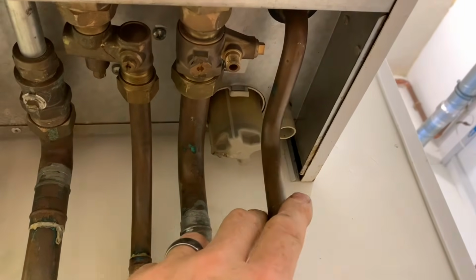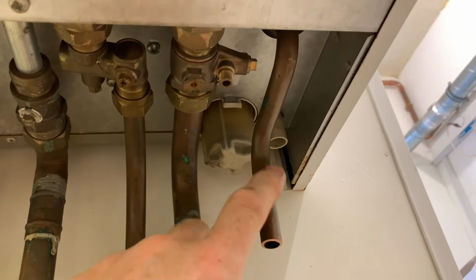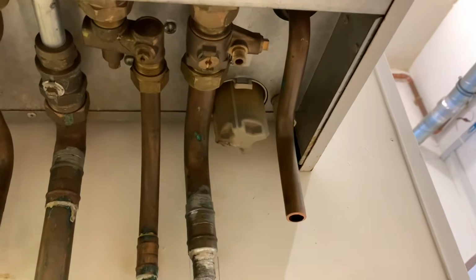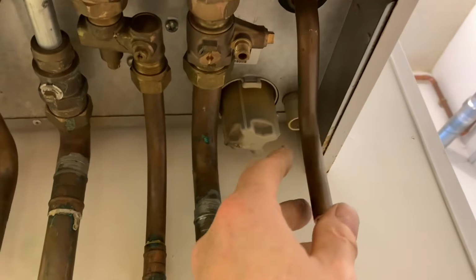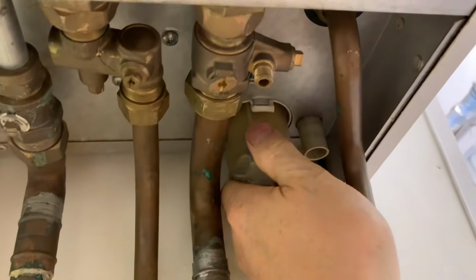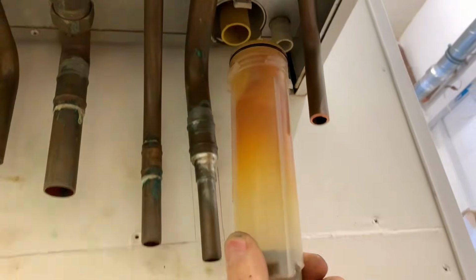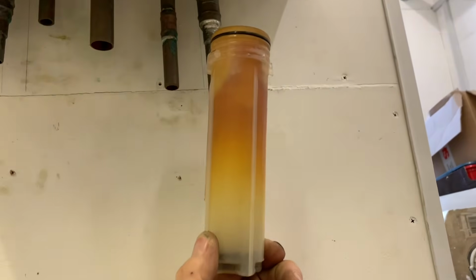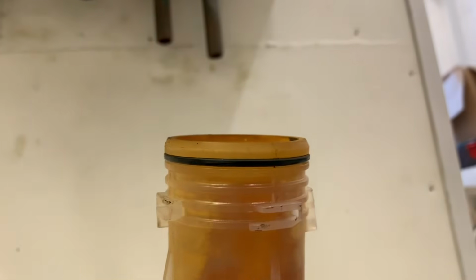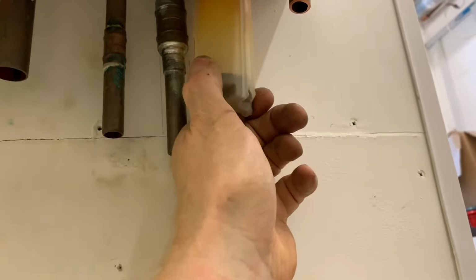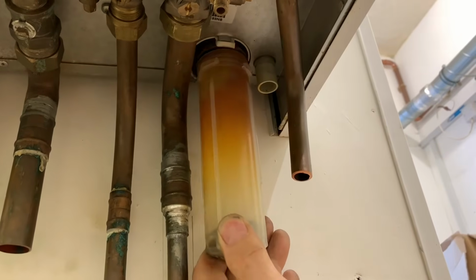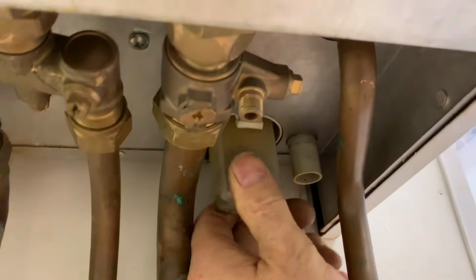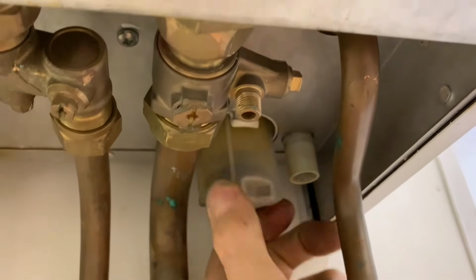Now this is the blow-off pipe. One of the things, this comes as a set length and you shouldn't cut it, because if you do cut it, you can't get this out. And this is the condensate trap. Now always again, another top tip, lube that up before you put it back up again. If you lube it up and push it in, it'll twist on dead easy.